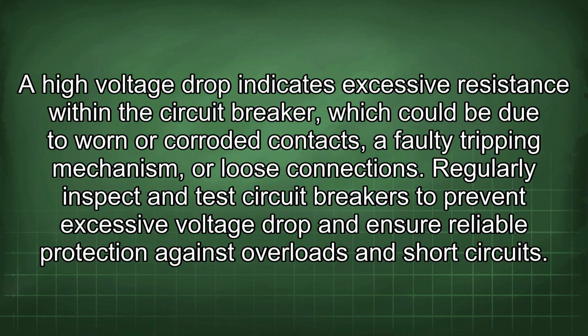A high voltage drop indicates excessive resistance within the circuit breaker, which could be due to worn or corroded contacts, a faulty tripping mechanism, or loose connections. Regularly inspect and test circuit breakers to prevent excessive voltage drop and ensure reliable protection against overloads and short circuits.